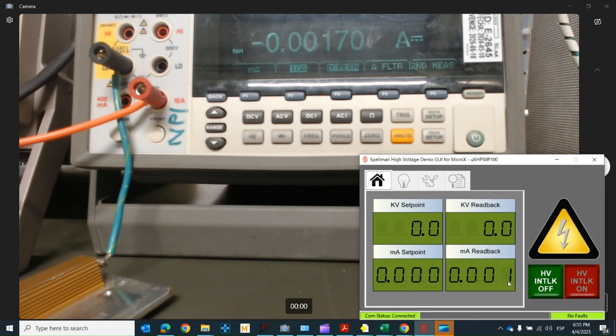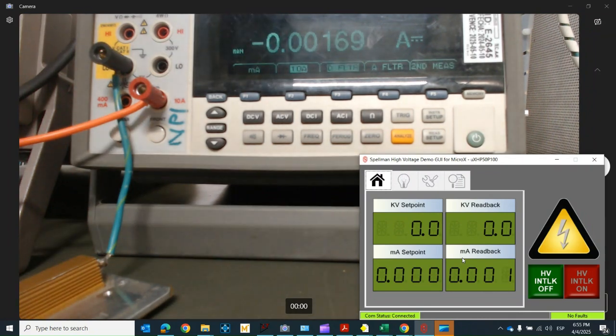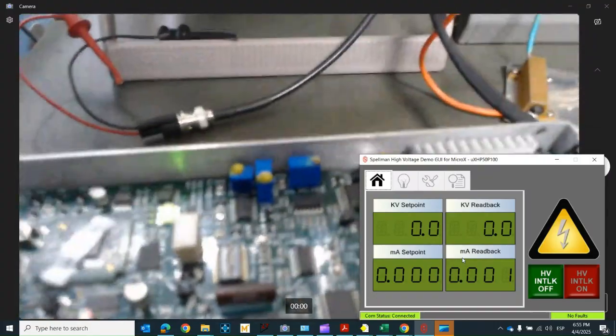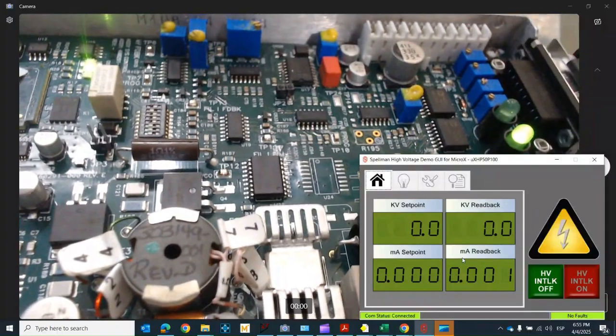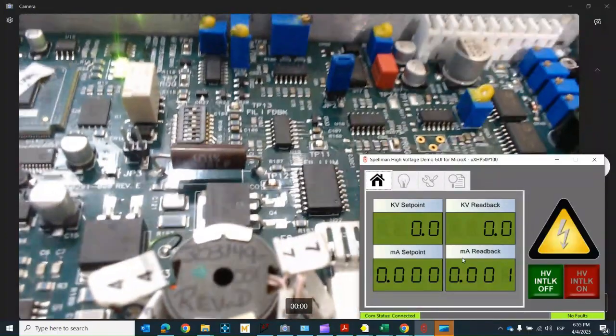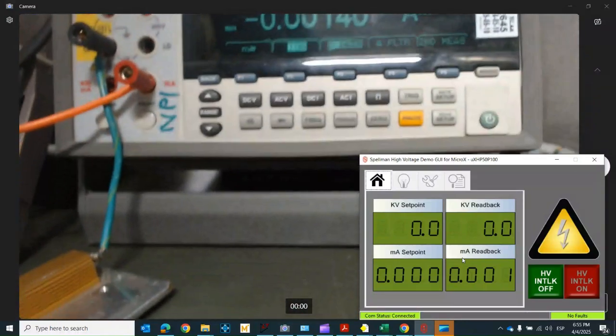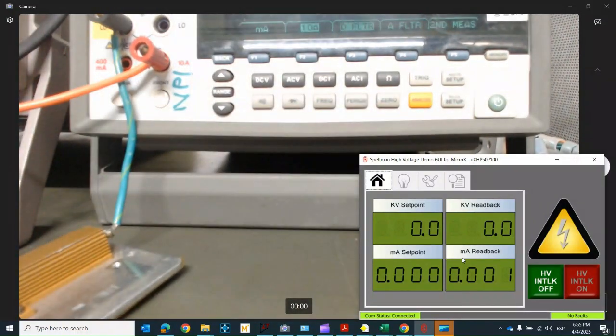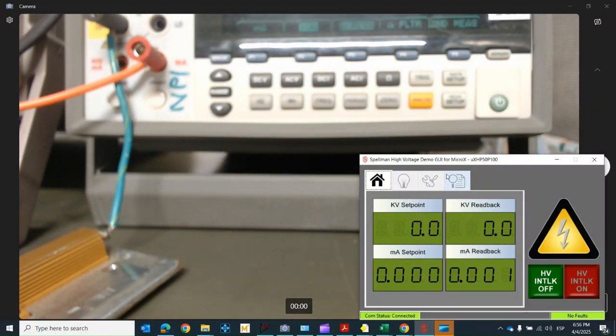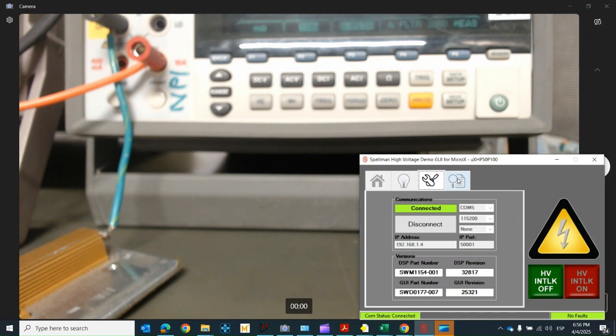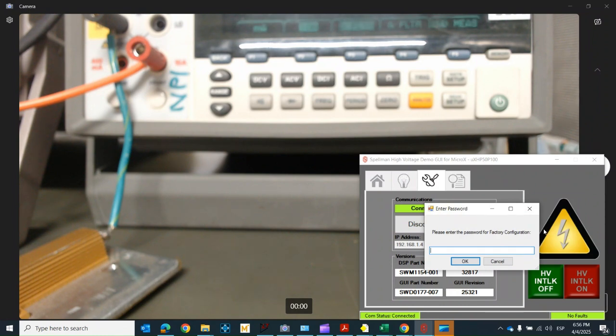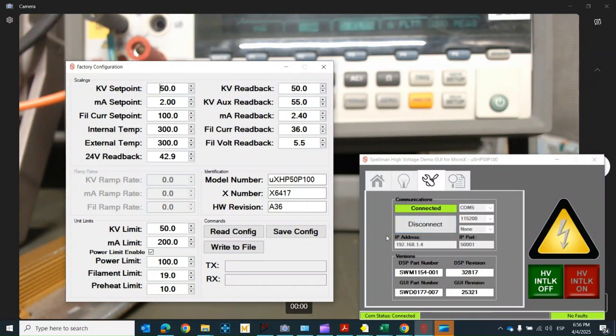In order to perform the overpower fault test, voltage monitor and mA monitor need to be present. This will be achieved by adding a jumper JP2 to the control PCB. After that, the factory settings menu needs to be accessed to change the power limitation to 25 watts. In order to do so, change power limit to 25 and click Save Config.